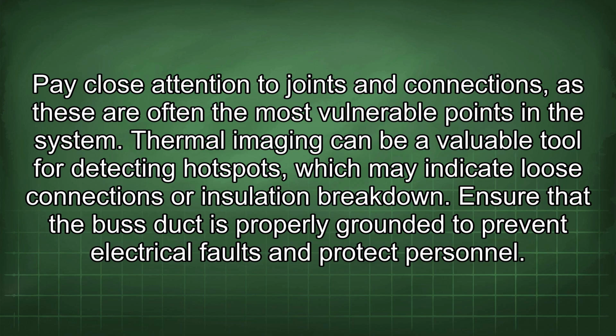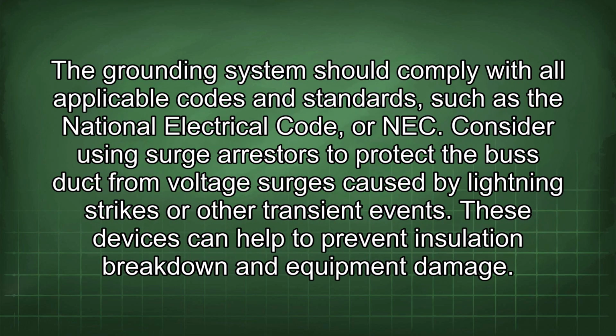Ensure that the bus duct is properly grounded to prevent electrical faults and protect personnel. The grounding system should comply with all applicable codes and standards, such as the National Electrical Code, or NEC. Consider using surge arresters to protect the bus duct from voltage surges caused by lightning strikes or other transient events. These devices can help to prevent insulation breakdown and equipment damage.